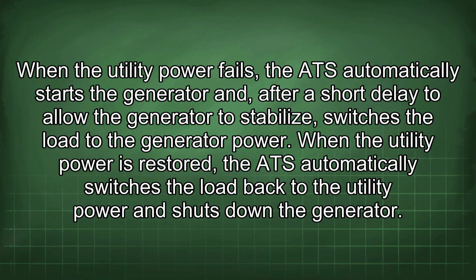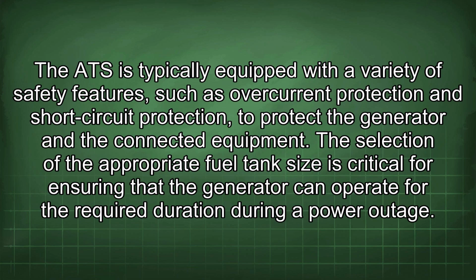When the utility power is restored, the ATS automatically switches the load back to the utility power and shuts down the generator. The ATS is typically equipped with a variety of safety features such as overcurrent protection and short-circuit protection to protect the generator and the connected equipment.